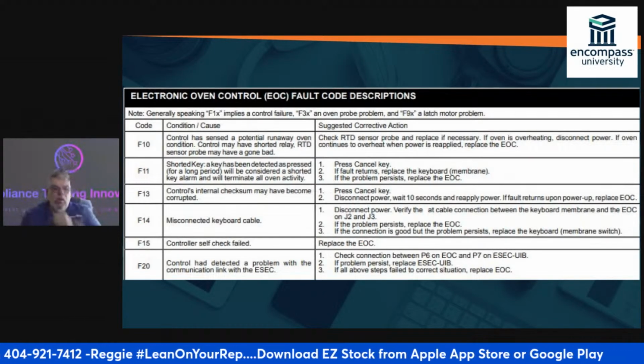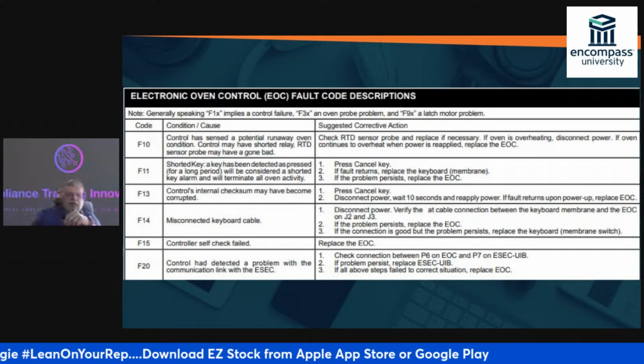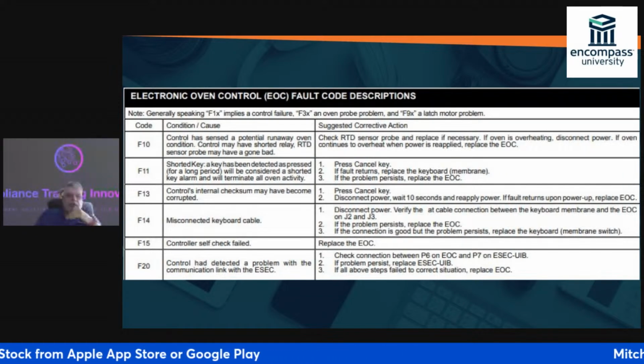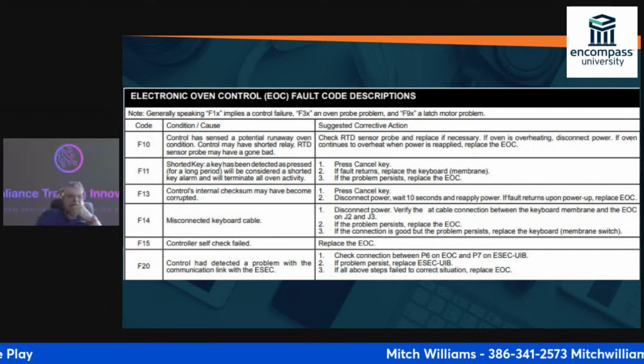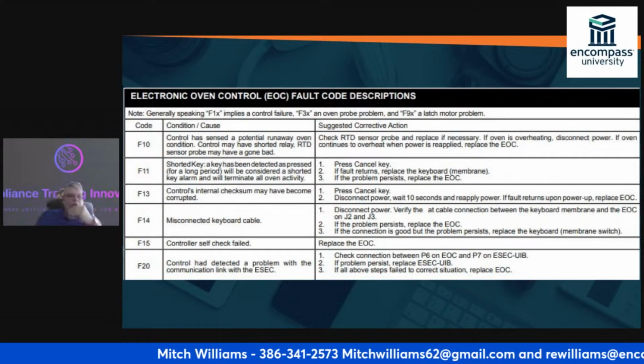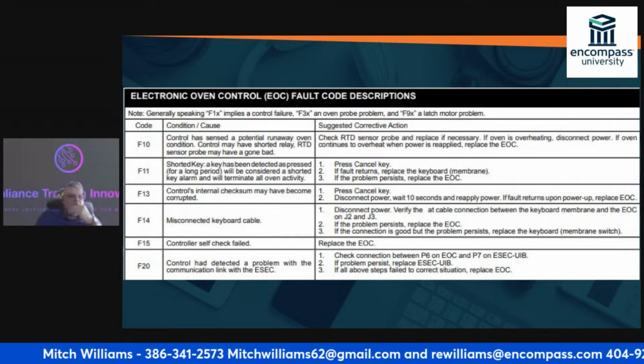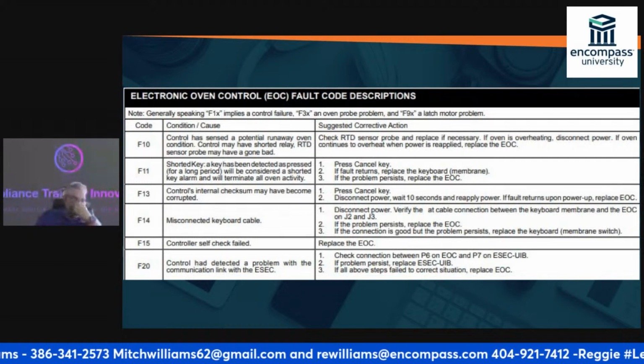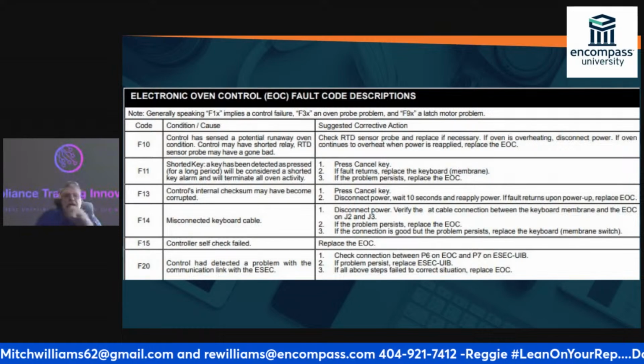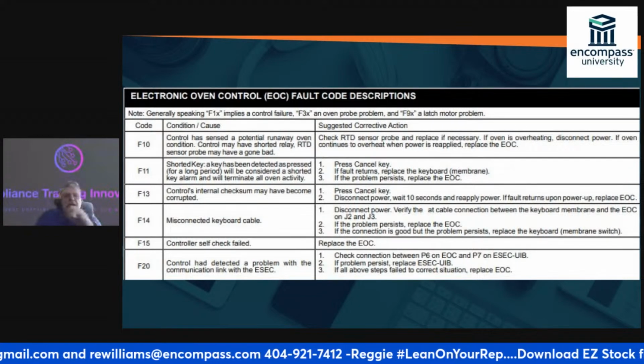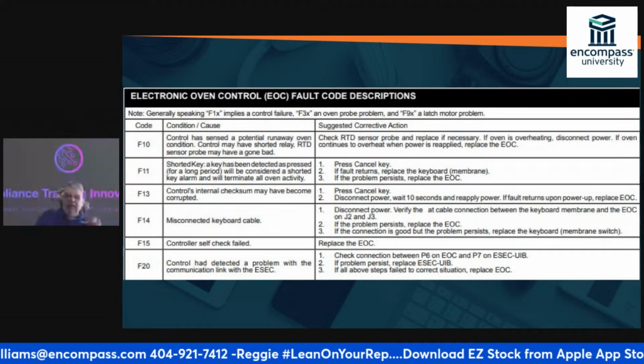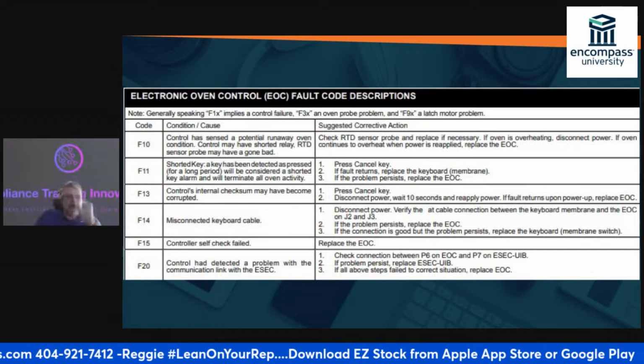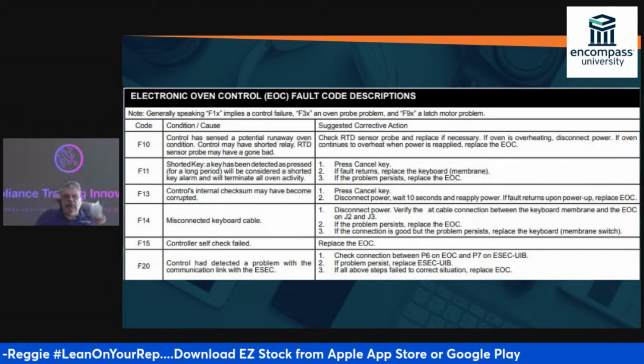So these are your fault codes. You're going to need these because when you go and you're trying to check this control, it will actually tell me what the problem is. So I know where to go check, and I need to check for an F10. I want to check the RTD sensor, okay? And if something happens and that RTD sensor checks incorrect, I'm going to go and I'm going to replace it. That's all I can do, okay?